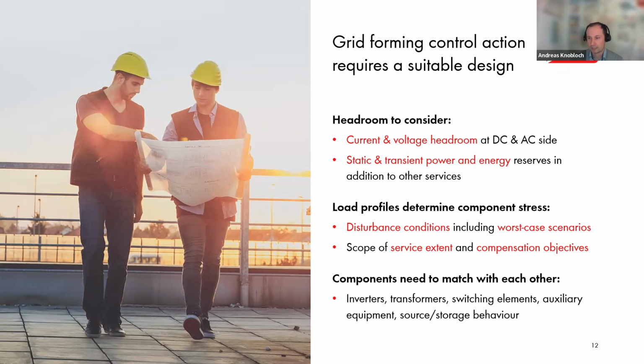Another aspect that is important within grid forming design is that the components your system is built of need to match with each other. So that means the inverters, the source or storage, the transformers, switching elements, auxiliary equipment, everything needs to match for being able to provide the grid forming services in a required manner or in a manner that you would like to do this.